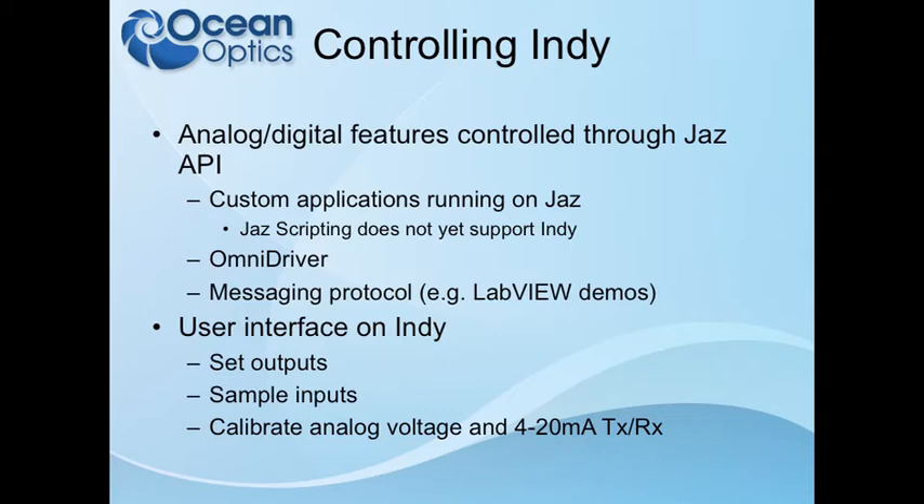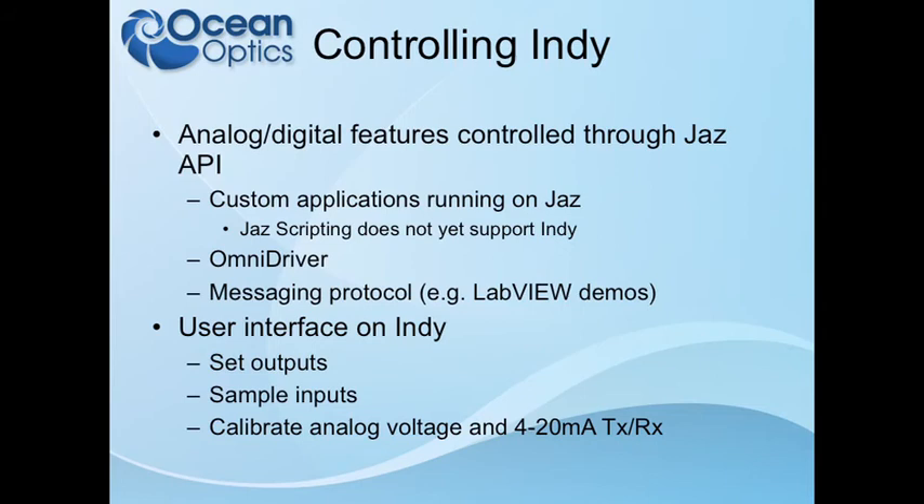How does one go about controlling the Indy? Generally, as with anything on the Jaz, the best way is to write a program that runs on the Jaz itself because then everything is fully integrated. Jaz scripting does not yet support Indy — that's planned for a later phase. OmniDriver can control the Indy, though the wrapper interface currently only has USB; Ethernet will be released soon. If you're using the Jaz API and generating messages in another programming language like LabVIEW, you can control it directly — the demo shown earlier where the gain was being controlled was a LabVIEW application talking to the Jaz using the messaging protocol directly.